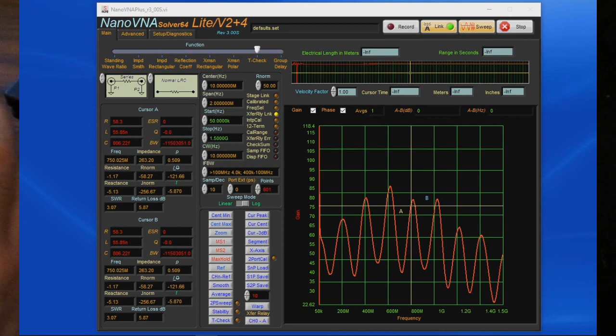So the next thing I'd like to do is run a full 2-port calibration. The way that we would do that is install a short, open, and load on port 1, and then again on port 2, and then we would install the through between the 2 ports. I'm not going to make you sit through that, so we already have the calibration performed. So we just select 2-port cal, we select old, we go to calibration, and we're going to select this 50 kilohertz to 1.5 gigahertz 2-port cal. And you can see it's now been calibrated. Next, we're going to rerun the T-check, but what I'd like you to notice is this 12-term LED right here.